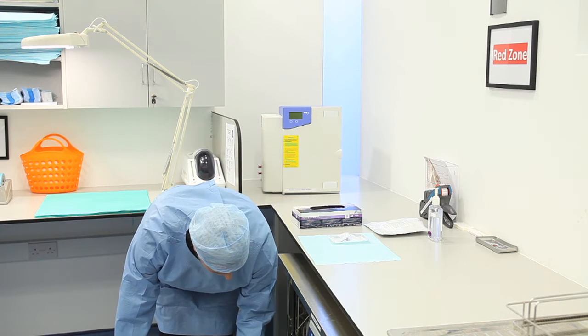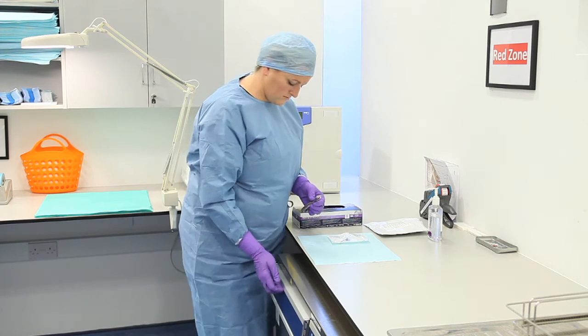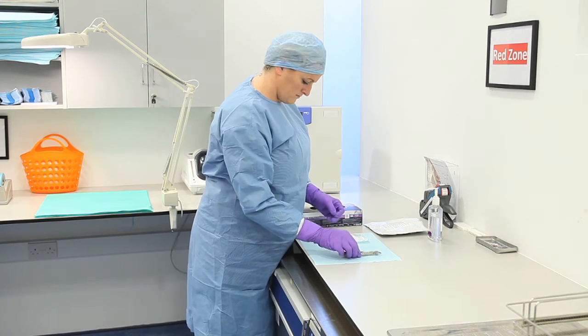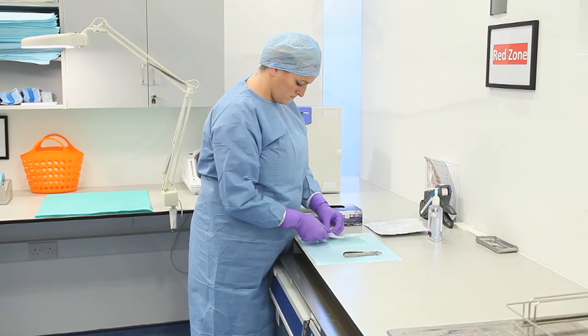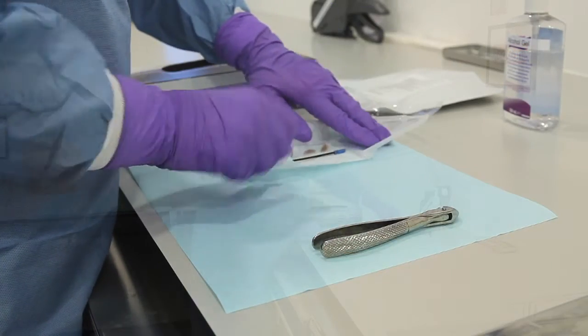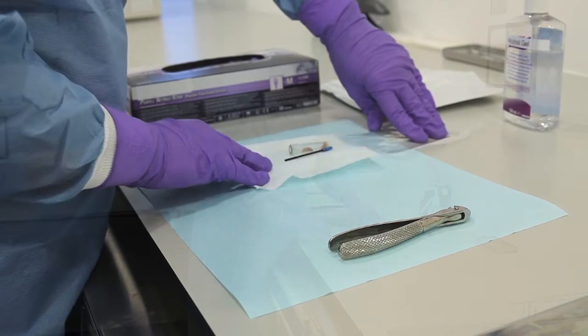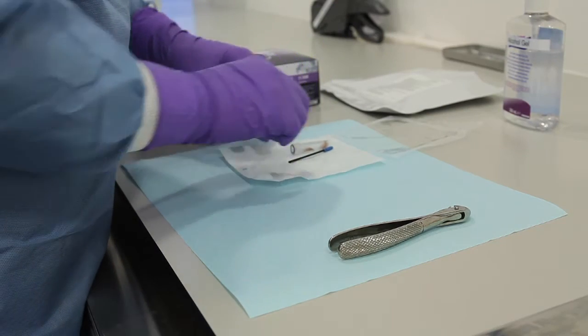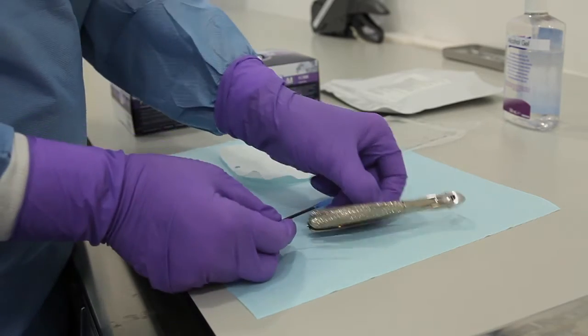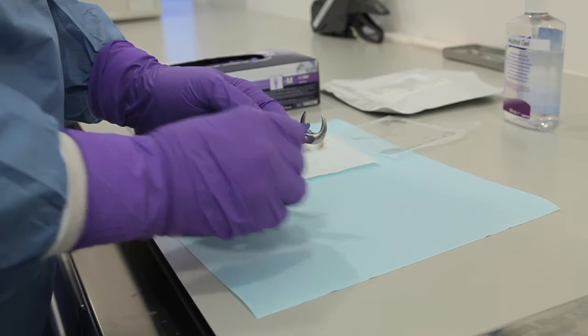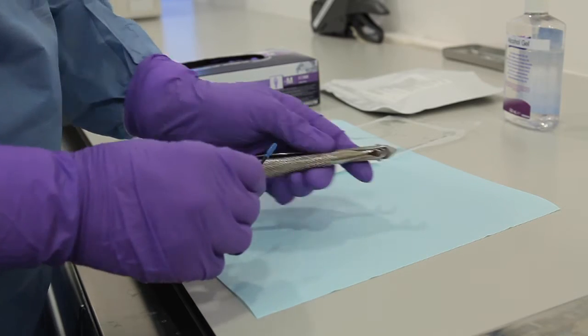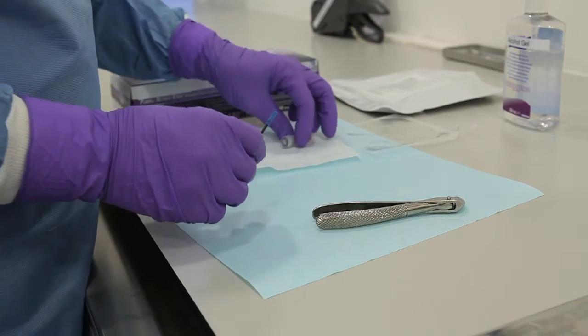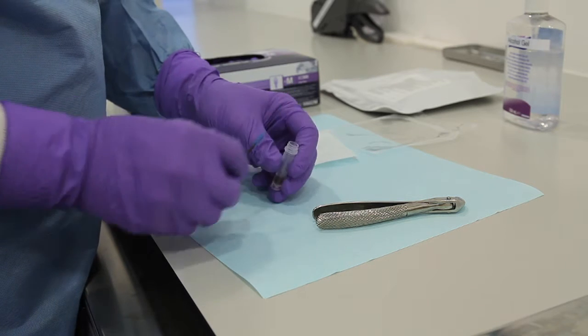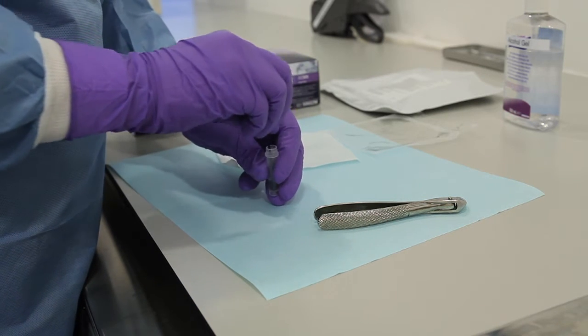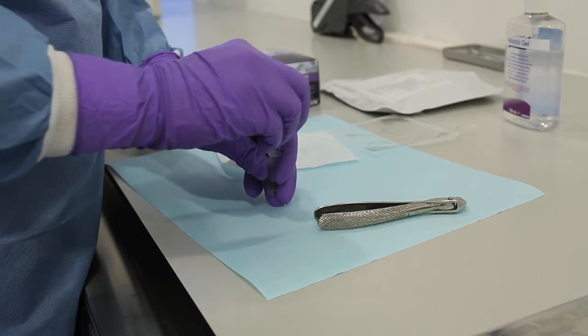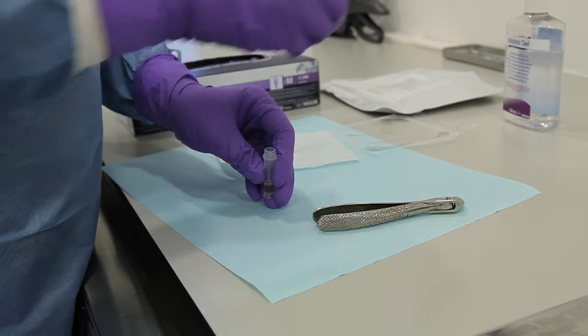Select an instrument which has been used during an invasive procedure, for example an extraction forceps. The manufacturer's instructions must be followed. Wear appropriate PPE as directed by the test manufacturer. To carry out a protein test, vigorously swab the RIMD using the test swab, focusing on hinges and crevices that may harbour traces of contamination. Unscrew the cap of the reagent container and swirl the swab in the liquid reagent for approximately 10 seconds. Remove and set aside the swab for discarding in the appropriate waste stream.